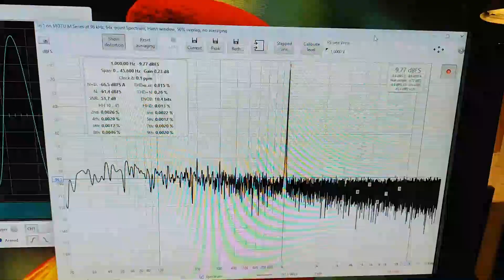First of all, you have to activate the generator and set up a 1 kHz frequency. You also need to activate the real-time analyzer and the oscilloscope. As you can see, we have the 1 kHz signal. The signal currently is coming from the input, so if I turn the input to output, we should not see any signal any longer.